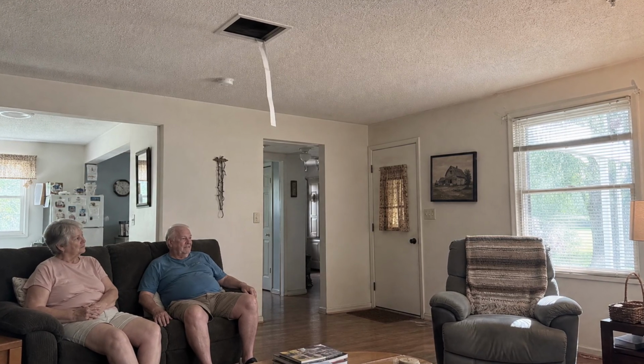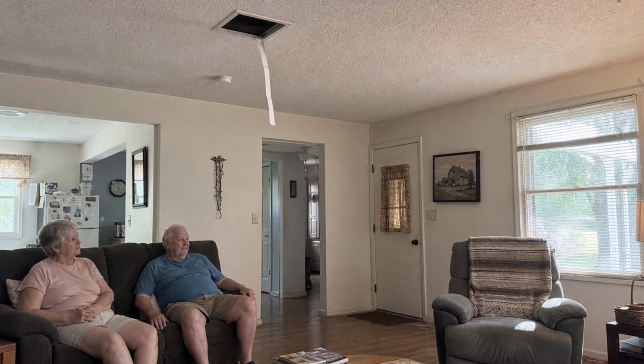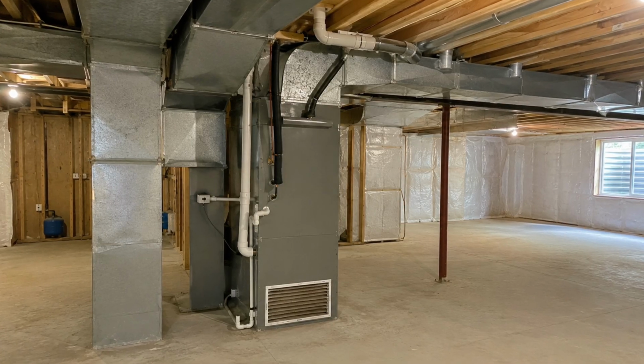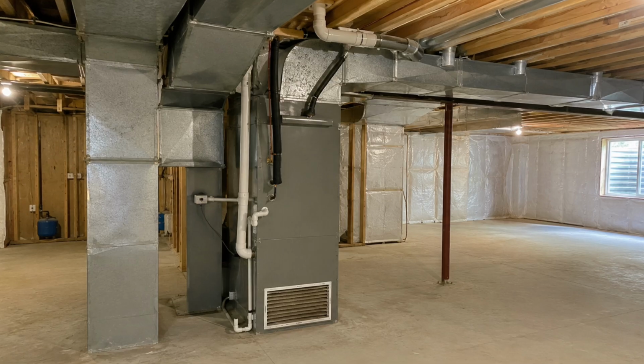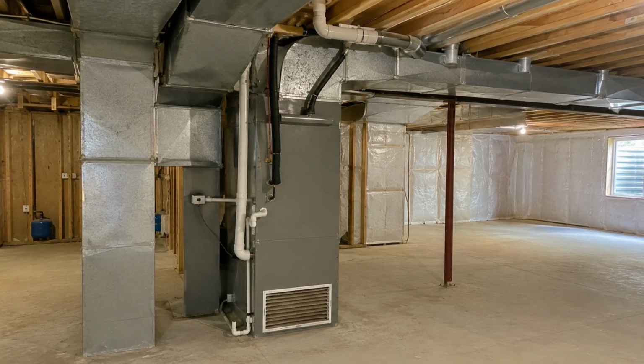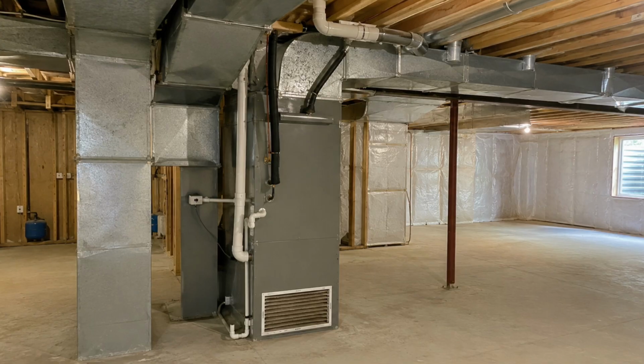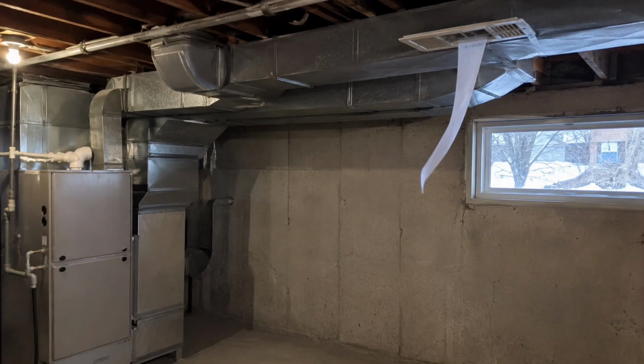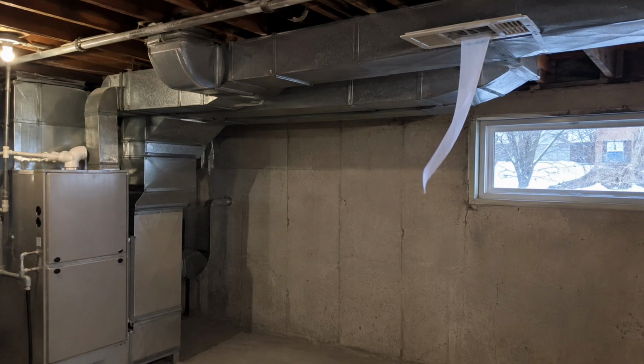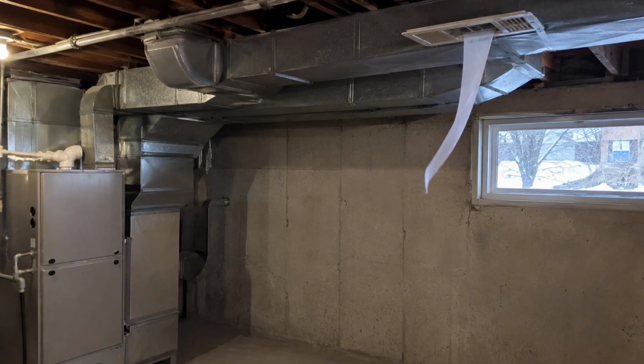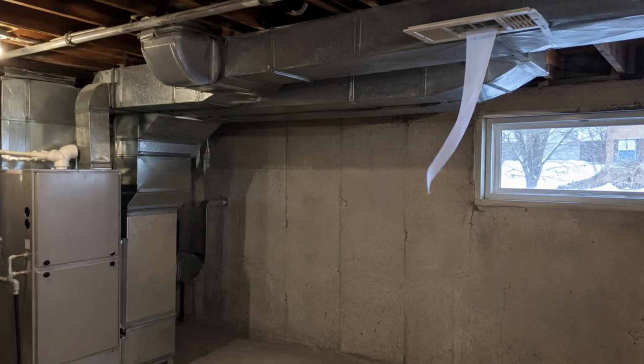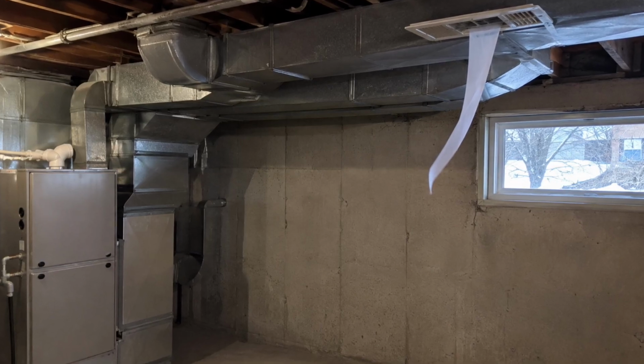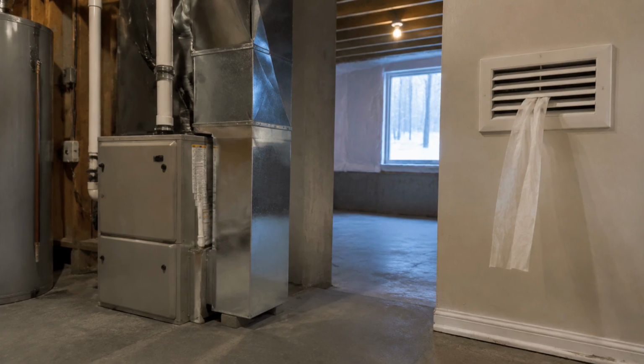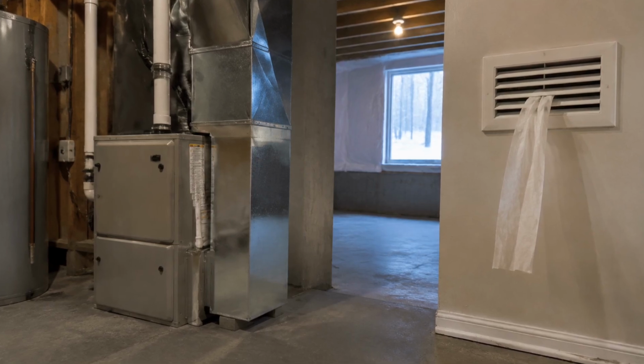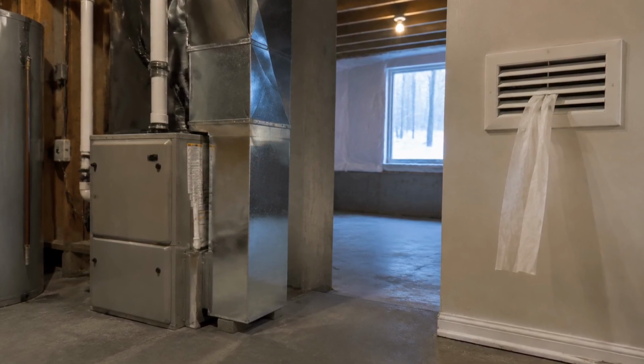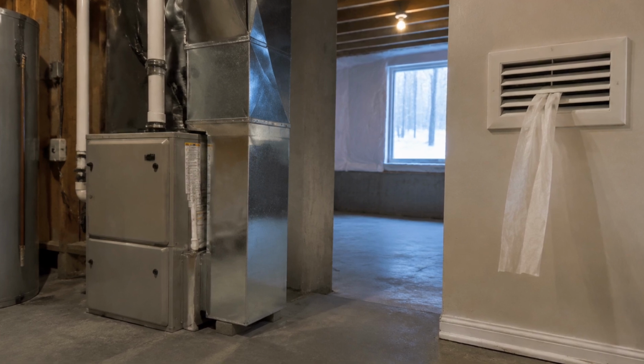One closed vent does not automatically freeze a coil. The risk depends on how many paths are restricted, how the ducts were built, how clean the filter and coil are, how the blower responds, and how close the system already was to its airflow limit. But low airflow is a well-known road to coil icing, and closed registers can add to that restriction. One sentence for winter, since the same tree often carries your heat. If too little air passes across a furnace heat exchanger, the furnace can run too hot and trip its high-limit safety. Repeated overheating is not something to ignore.